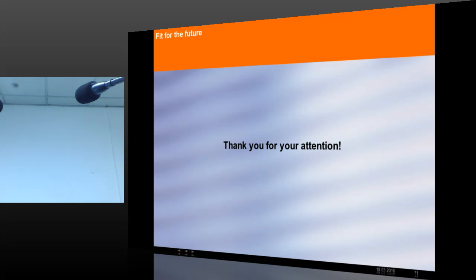So, what is the recommendation for an extra downconductor, maybe instead of using a natural conductor? That is the first question, and another is what is the good way for bonding the rebar of a natural conductor, with exothermic or a clamp? Exothermic is the best. Please note, exothermic is the best, but the problem is, if you imagine a building of that height, which needs thousands of connections, doing exothermic welding will be very difficult. No, I know. For the extra downconductor we can use, how should the earth point and the downconductor be connected, exothermic or clamp?